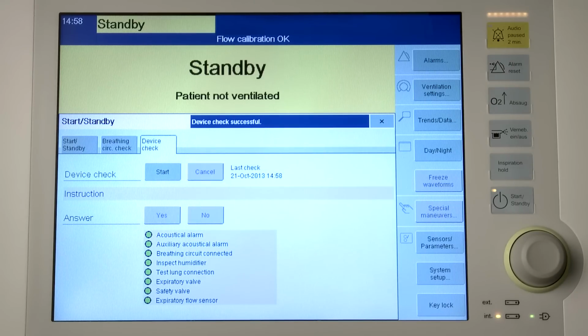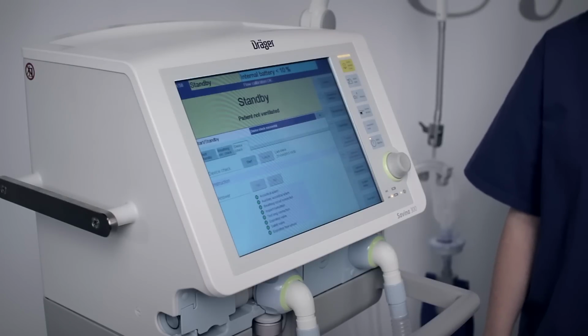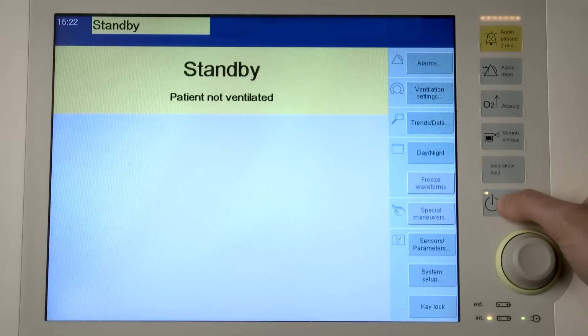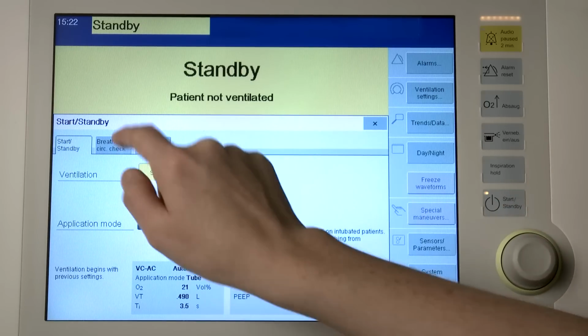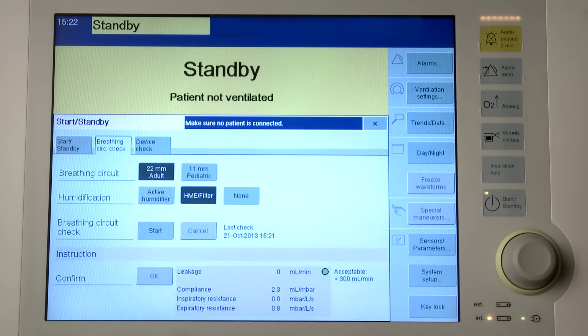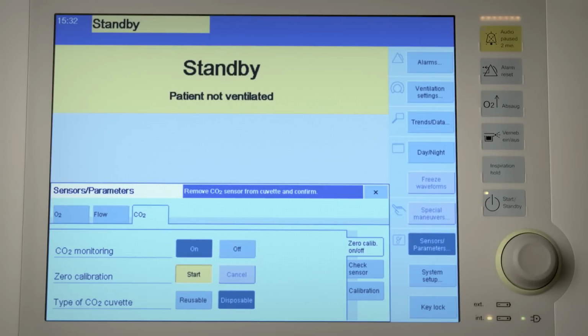After the device check was successful, perform a breathing circuit check. For the breathing circuit check, Savina 300 has to be in standby mode. You already selected the breathing circuit and the humidification type. Touch the breathing circuit check tab. Savina 300 displays the values of the last test. Touch the Start button and confirm with the rotary knob. Now follow the instructions displayed in the instruction field.